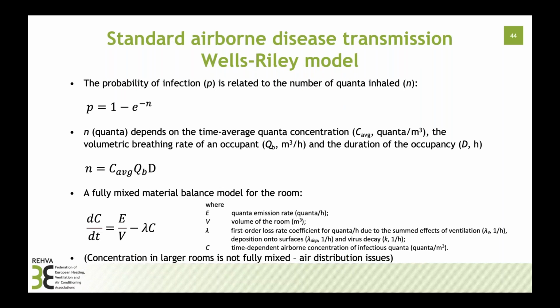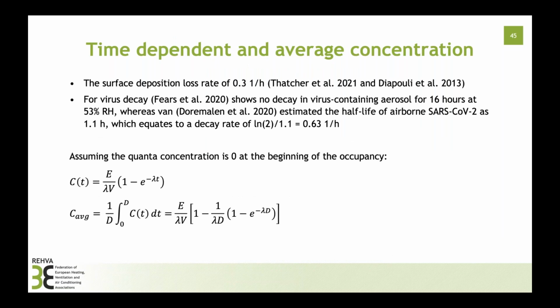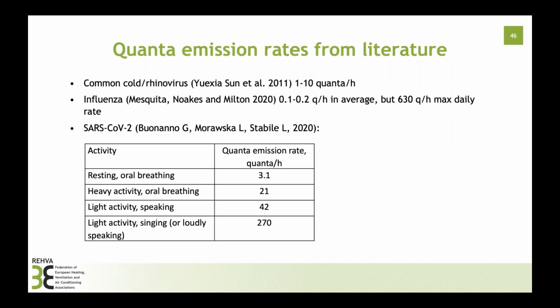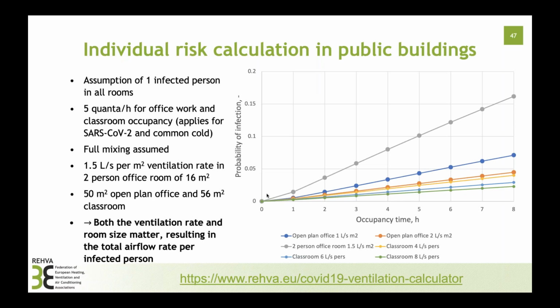So that's the motivation to calculate this infection risk, which can be done with the Wells-Riley model, which is quite well known, but then needs to be calibrated to a specific virus. This can be applied for the common cold, influenza or SARS-CoV-2. No difference, these are all airborne viruses, but the quanta emission rate is virus specific and also activity specific. If a person is sitting doing office work, not speaking, the emission rate is very low, but it can be 100 times higher if somebody is singing or loudly speaking, and physical activity will also increase the emission. That makes this calculation a bit complicated, because we don't know these quanta emission rates so well for this specific virus, but some estimates can be done.